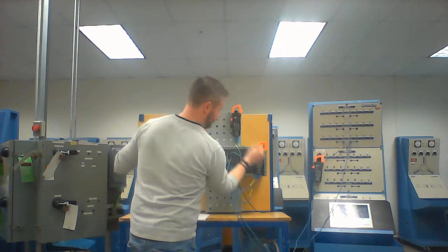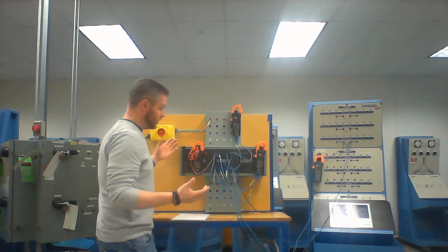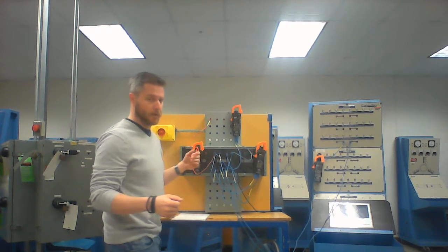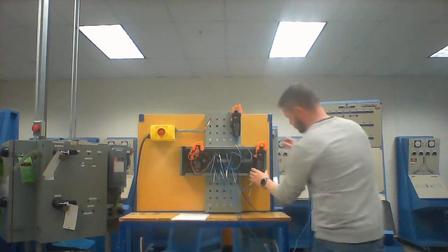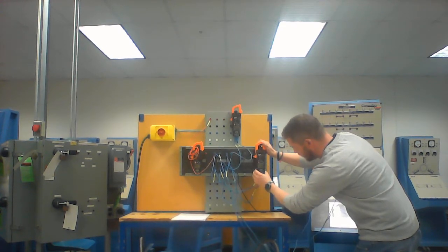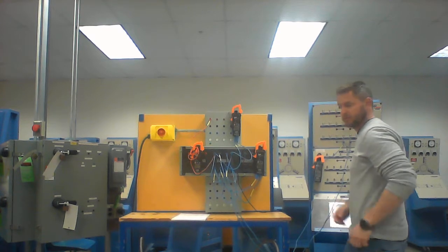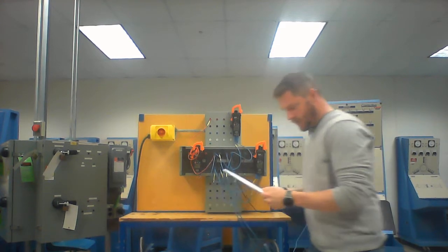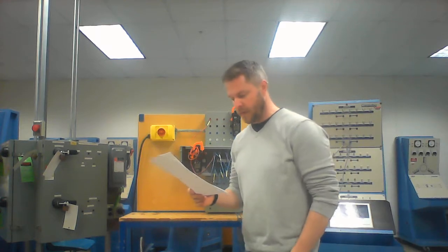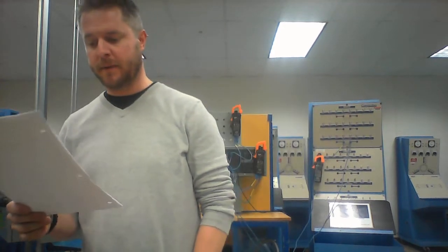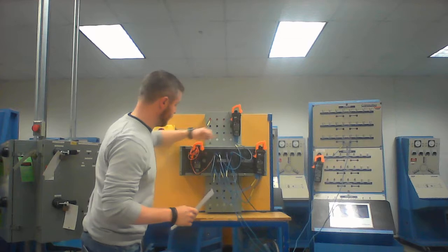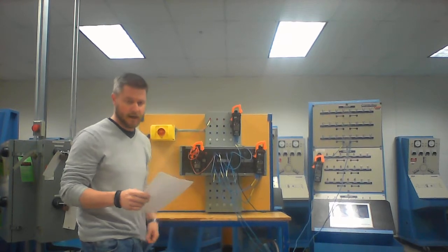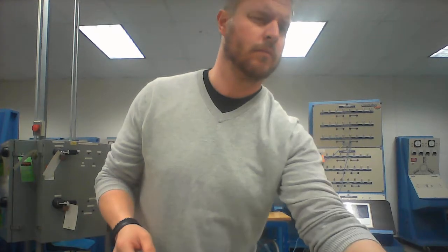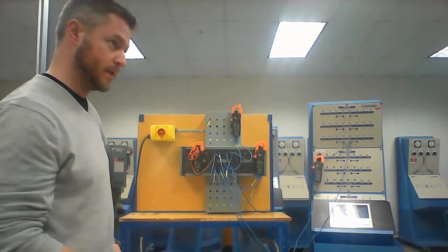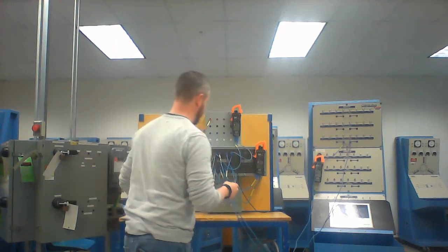Meters keep turning off. Primary voltage, exactly 204. And secondary voltage, 125.2. Okay. Given that, I'm going to calculate my voltage ratio by dividing the primary voltage by the secondary voltage and figure out what my turns ratio is for my specific transformer here using my 204 and my 125. Mr. Mankulich, if I do that, I get somewhere around 1.629 to 1. Awesome.